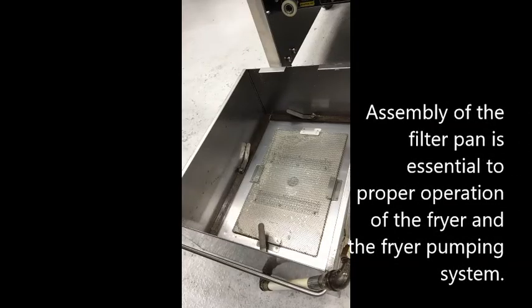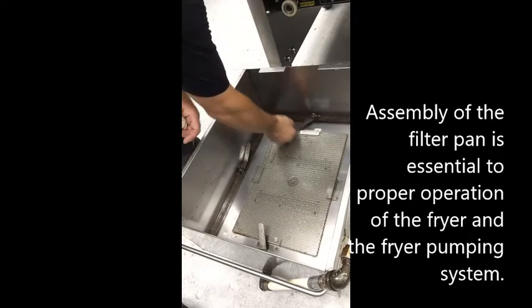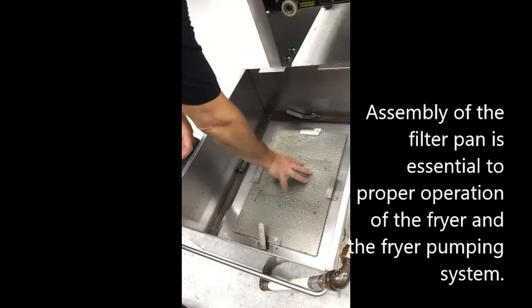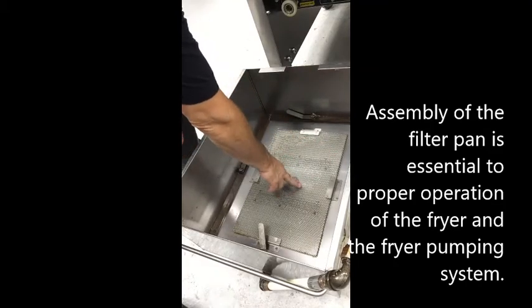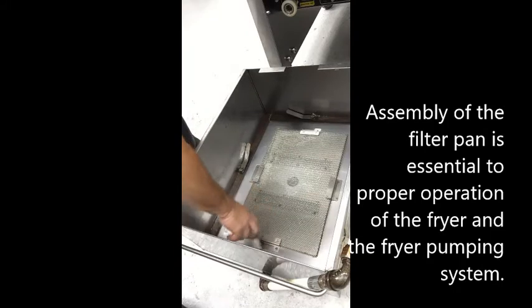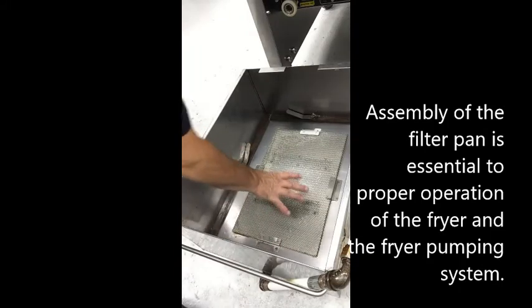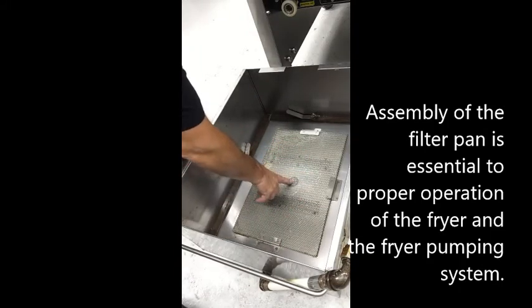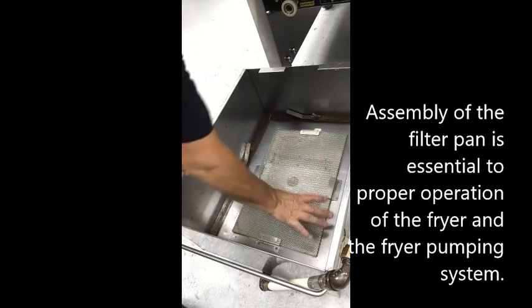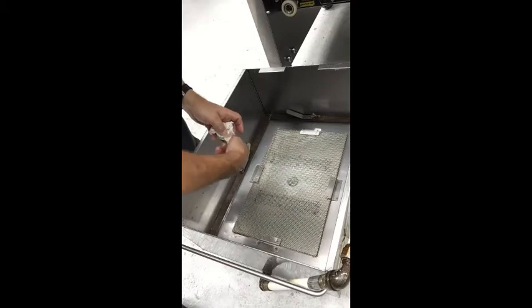Now we want to talk about the filter pan and the kind of issues that you'll have if it's not put together right. You'll notice that there's 4 of these little latches in the bottom of this pan. This screen in the bottom is welded in. It's welded so that they can't lift it out. And it keeps the paper from being sucked against the bottom because you're pulling from right here in the center. So it allows that oil to go down through, leaving the sediment on top of the paper.